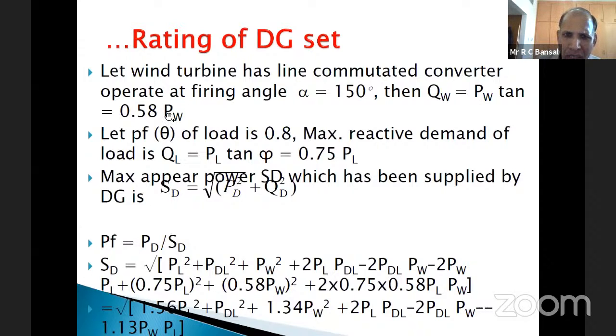You have to consider the power factor of the system. Based on the power factor, you calculate the angles and accordingly find the apparent power rating. So as I mentioned, the apparent power rating of the diesel generator equals P plus JQ, or equivalently the square root of P_D squared plus Q_D squared, where D stands for diesel. That determines the rating of the diesel generator.